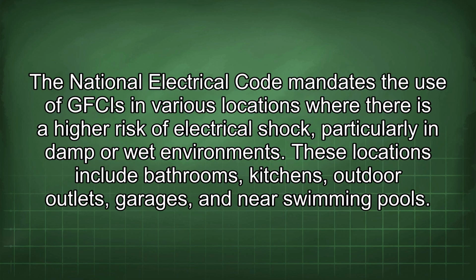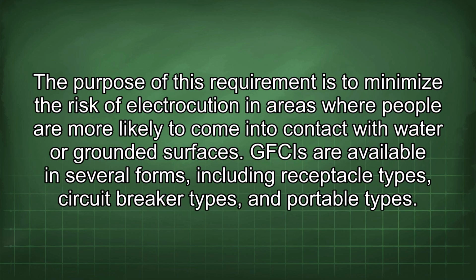The National Electrical Code mandates the use of GFCIs in various locations where there is a higher risk of electrical shock, particularly in damp or wet environments. These locations include bathrooms, kitchens, outdoor outlets, garages, and near swimming pools. The purpose of this requirement is to minimize the risk of electrocution in areas where people are more likely to come into contact with water or grounded surfaces.